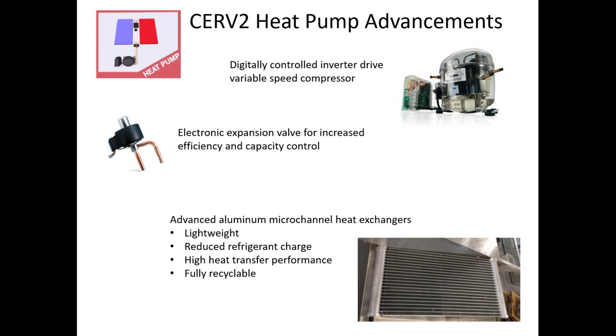Just quickly over what the heat pump is, we have a digitally controlled inverter drive, so it's variable speed. We can optimize the efficiency depending on the conditions. There's also an electronic expansion valve that lets us do this further. We use aluminum microchannel heat exchangers, so we have very low refrigerant charge, with very good heat transfer performance and airflow.